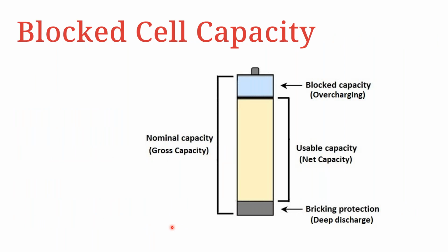With regards to the previous slides, we now want to inform you about what we call blocked cell capacity. For large capacity batteries, with reference to specific energy density, it is required that some part of the battery is blocked. This is what we call the non-usable part of the battery. That is why, in most cases, when we look at battery nameplates, we see what is called usable capacity. So you could have a battery that is, say, 27 kilowatt hour, but they will tell you the usable capacity is 20 kilowatt hour. This means some specific capacity has been blocked off, and this is done to elongate the lifespan of the battery.